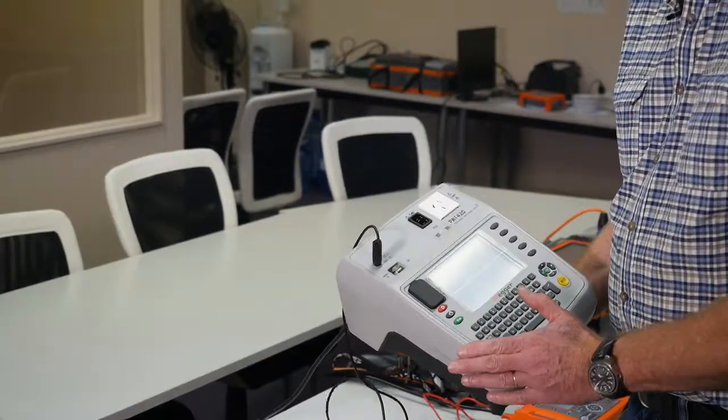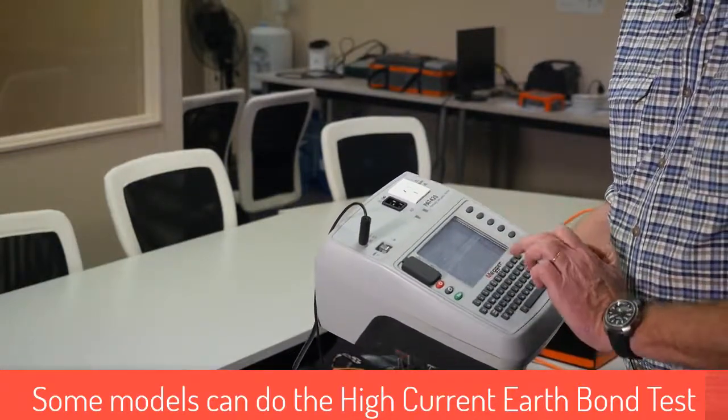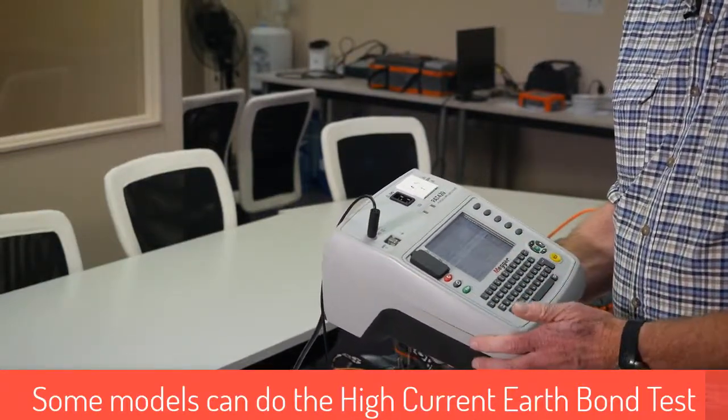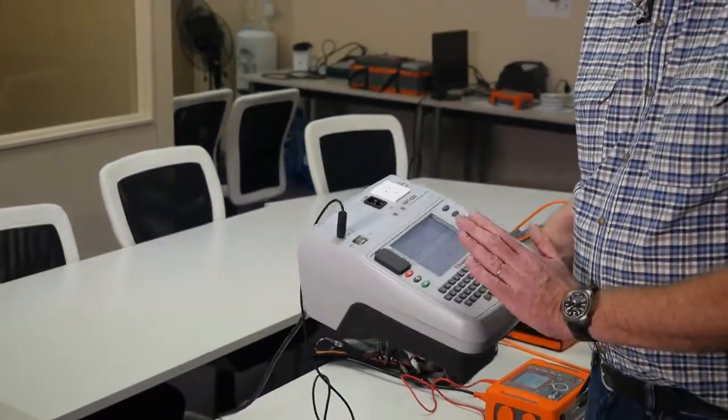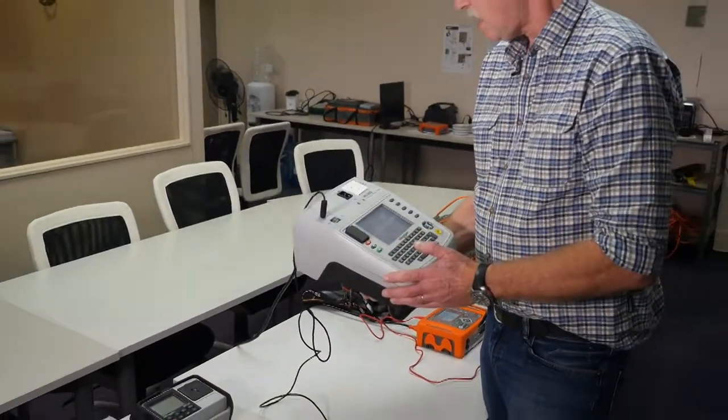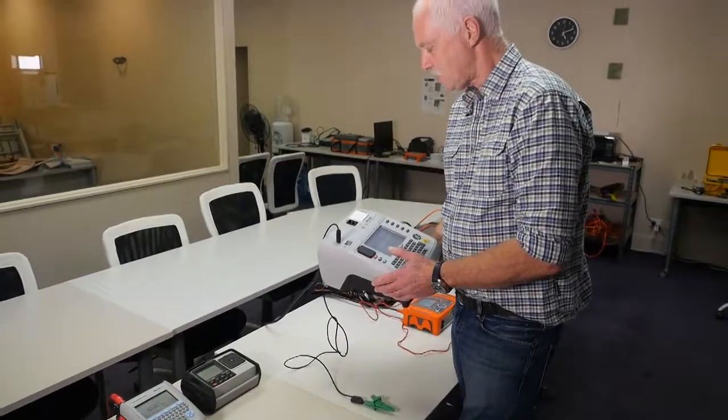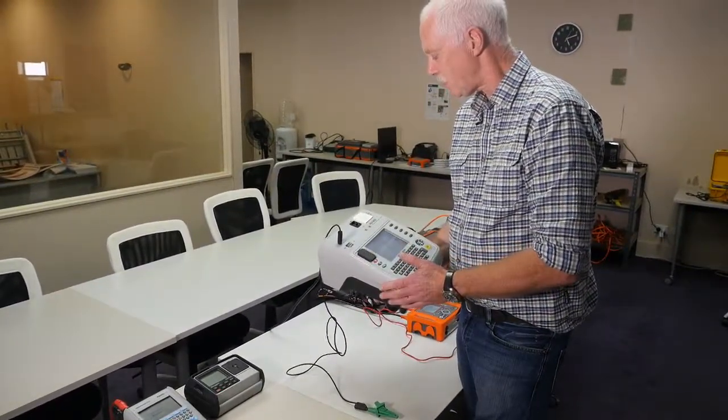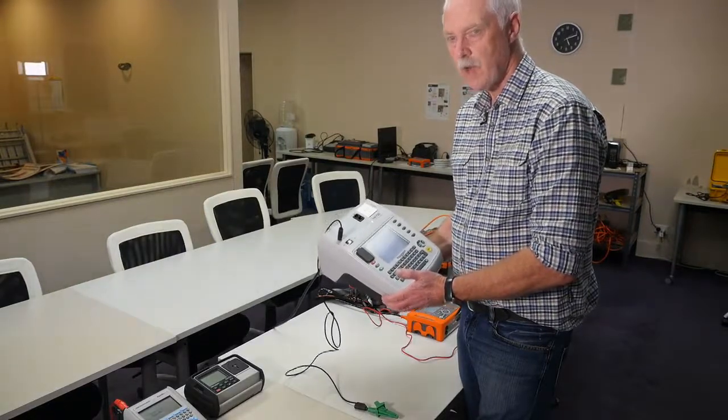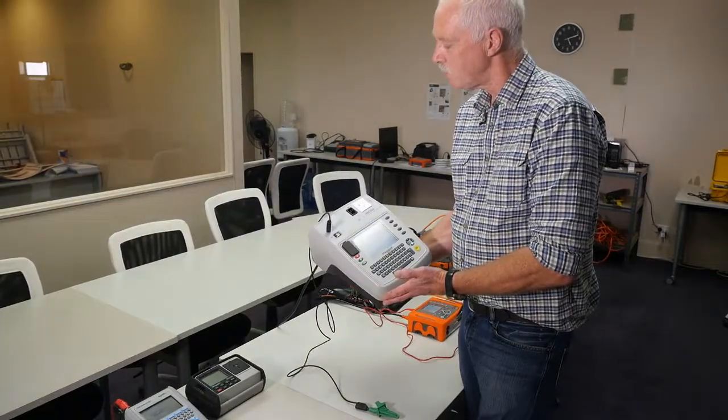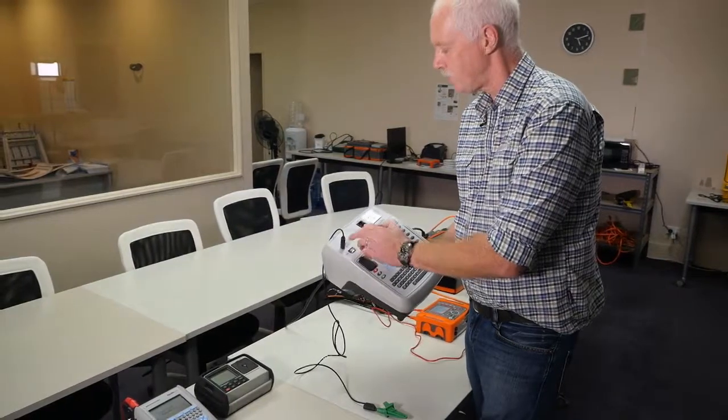This model comes in two different types. So it can do a high current test. Some of the models can, and some of them will only do a 200 milliamp earth bond test. It's got a memory of, I think from memory it's about 15,000 items. And it can do pretty much every test that you need it to do. What it can't do in the low current version, obviously, is a high current earth bond test. But there's two different versions. One has the high current and one doesn't. It looks very much the same. So if you're looking for them, you need to make sure that it says at the top that it can do a 25 amp earth bond.